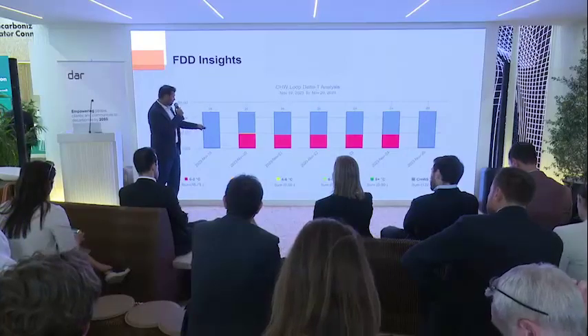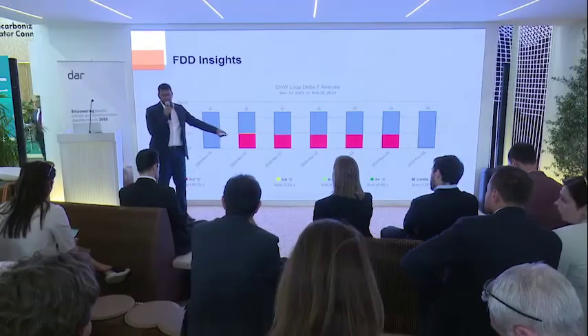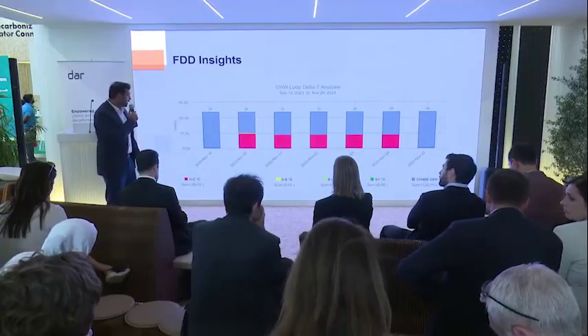You can see on a daily basis that's 24 hours. Makes sense. So you have, I think this is a Sunday, and the last day there is a Saturday. So on weekends, you have the plant completely turned off. And then this is during the shoulder season. I actually captured this image just before I traveled here, end of November. What you're seeing in this real world building, this building is located in Canada, and you can see during the winter season, there is really low demand.